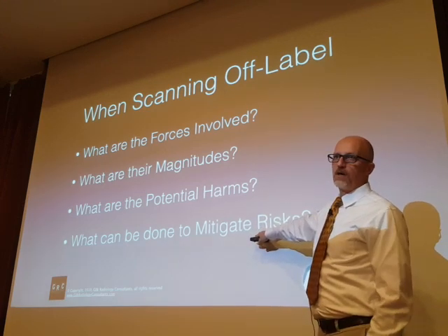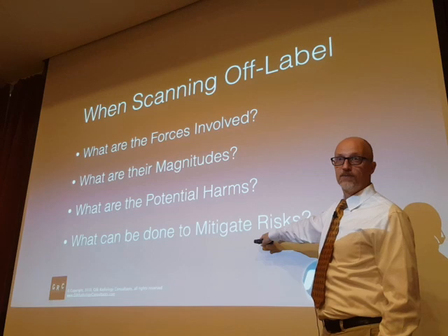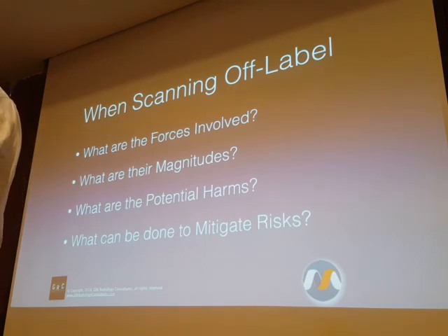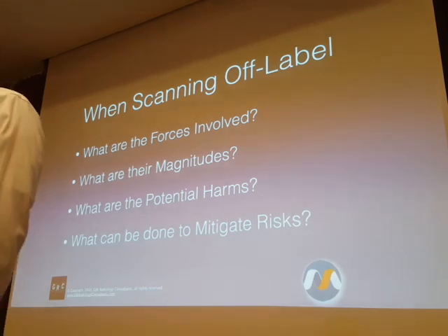If you identify risks, is there anything you can do to mitigate them? Can you modify the study, change the pulse sequences, reduce a flip angle? While you can't really quantify it, if your scanner has a silent or quiet mode, that dramatically reduces the gradient level. It won't tell you by how much, but if you have concerns and you know one option is significantly less than another — even if you can't assign numbers — that may be enough comfort to proceed using a silent scan protocol if you're concerned about gradient-related forces.